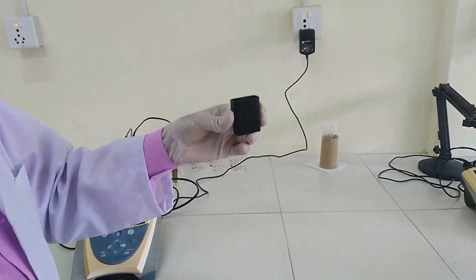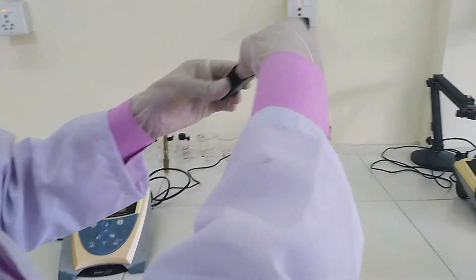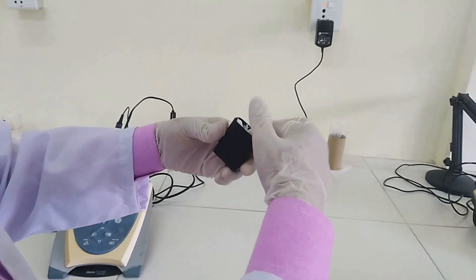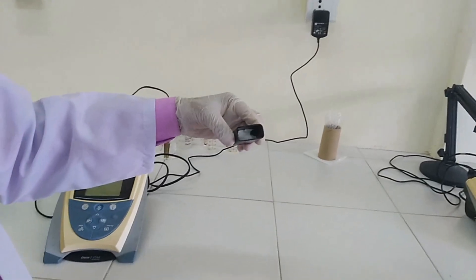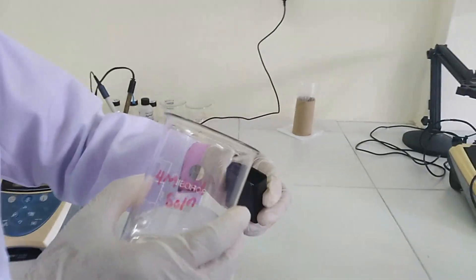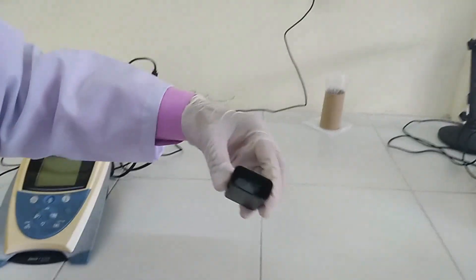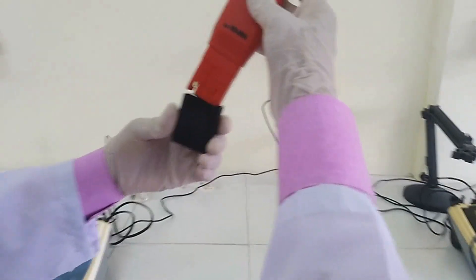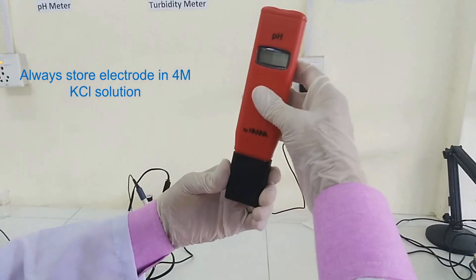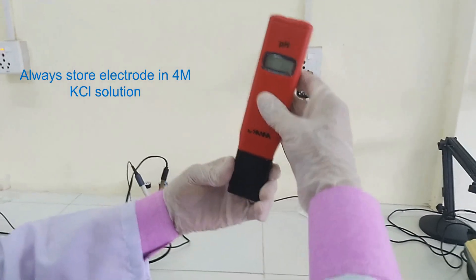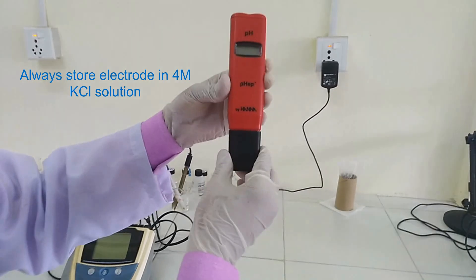Never store the pH meter dry. So take a small piece of tissue paper in cap, wet it by 4 molar potassium chloride storage solution and insert the instrument in cap and store. Thank you for watching.